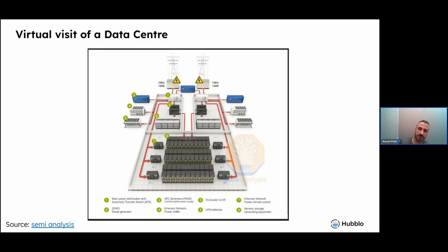The batteries can be used as a second energy source, but their capacity is very short - you won't run your full data center for several days on batteries, more like minutes or hours in the best case. At some point you'll have to switch to the third power source if there's an issue: the backup power generators, which you see in blue in the back as well.